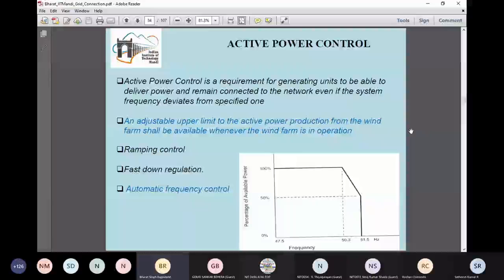Then the next one is the ramping control. Ramping control is that when the wind starts blowing, the wind speed can suddenly change from very low to high, but the output of the overall wind farm should be controlled at a certain rate. It should not go suddenly as a step increase in the output power. So this is known as ramping control.